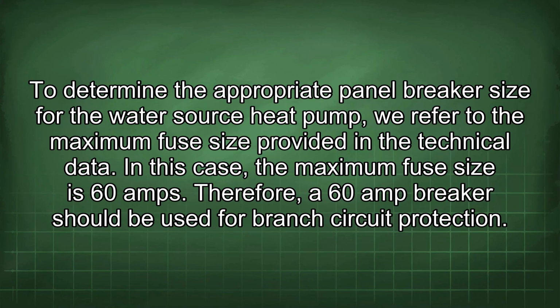To determine the appropriate panel breaker size for the water source heat pump, we refer to the maximum fuse size provided in the technical data. In this case, the maximum fuse size is 60 amps. Therefore, a 60 amp breaker should be used for branch circuit protection.